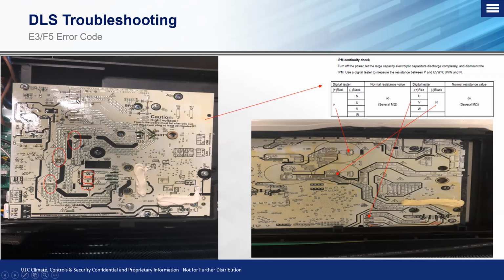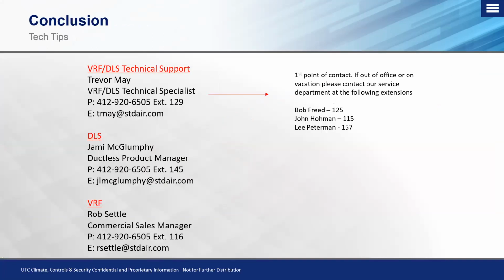If you have incoming voltage to this board, let's just say we took a reading and it was 232 into the board, but these lights aren't lit up on here, a red or a green, chances are your drive board has failed. And that's a really easy way to tell if you have a failed drive board, outside of course of checking to make sure your capacitor buses are okay, and then also the path from the capacitor buses either to your compressor or to your outdoor fan motor. So hopefully you guys took something out of that. You have a little bit more confidence troubleshooting the outdoor fan motor and also understanding how that power flows through the main PCB, and if you have a split type board, from the main PCB to the inverter drive to your outdoor fan motor.